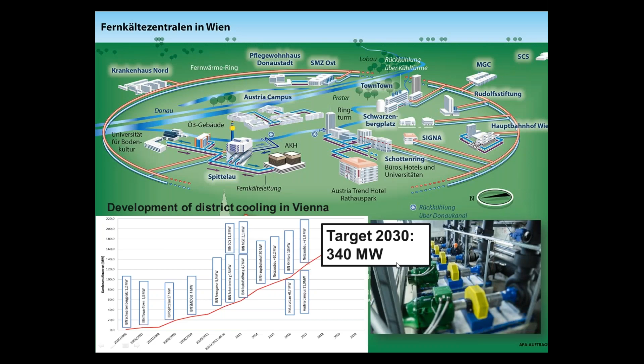Some technical details: the Spittelau plant, which I want to mention in detail, has two absorption chillers and one electrical chiller. The absorption chillers are powered by the waste incineration. We have 140 degrees there - normally we have less, around 95 degrees, but in this special case we have 140 degrees. We produce cold water in the flow at 3.5 degrees, and supply it via a district cooling network to our customers. They have a heat exchanger there, and we supply them with 6 degree cold water.